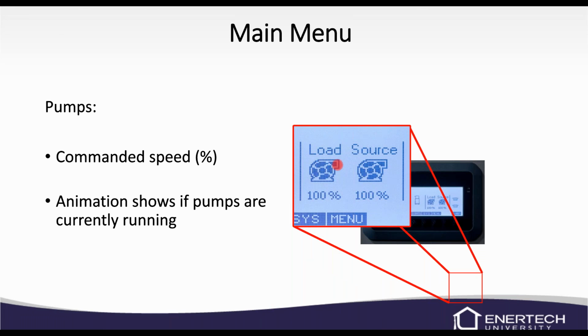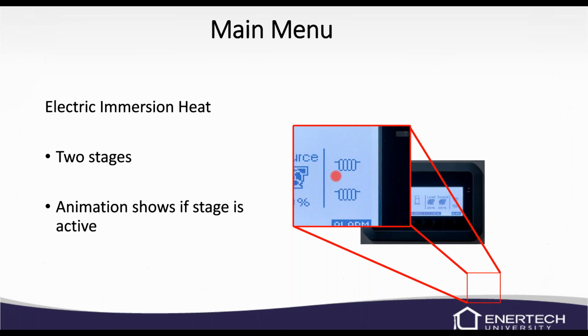The pumps, obviously this is a load pump, source pump, they're at 100%. These little black boxes that are kind of around the volute will spin, so there will be some animation here as well if the pumps are running. And then these are your electric heaters, first stage, second stage, and these will have black bars in them if they are calling. So if first stage is calling, all four of these bars will be a darker color. And if the second stage of the electric heat is on, then these black bars would be on as well.